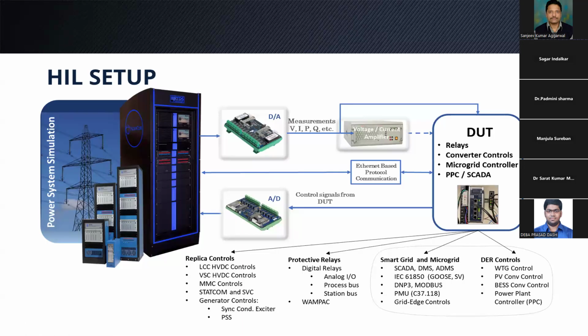And then you will not only be able to test the performance of the relay, whether it took the right decision or not, you will also be able to check whether that decision deteriorated the network condition or not. For example, you opened the breaker and that leads to system imbalance, right? That can also be checked. And then you can also check whether the relay was able to withstand that disturbance, that voltage or system imbalance. So this is closed loop testing of a physical device in a simulator. And to do that, RTDS requires dedicated hardware. That hardware is basically a very powerful processor, which is housed inside this chassis. This is called a NovaCor. It has an IBM processor, which can solve all this network in real time.